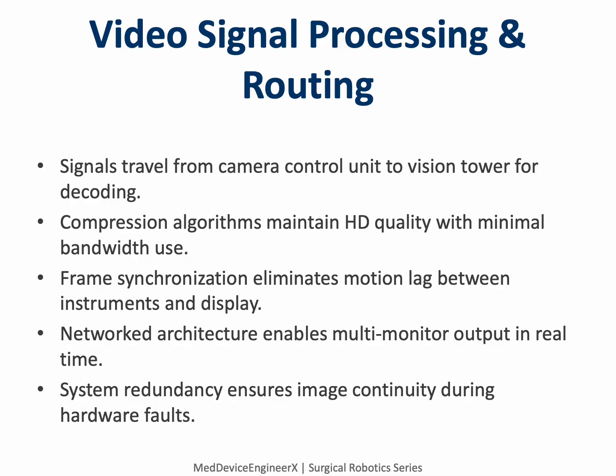Once light becomes data, the challenge shifts to managing that information efficiently. Video signals from the camera control unit enter the tower through high-speed digital links, where they're decoded and processed in real time. Advanced compression preserves full HD quality while minimizing data load on internal networks. Each frame is synchronized through instrument motion, eliminating perceptible lag and keeping the visual field perfectly aligned with robotic response. The processed video can be routed simultaneously to multiple displays, the main console, assist monitors, or external recording systems for teaching and analysis.